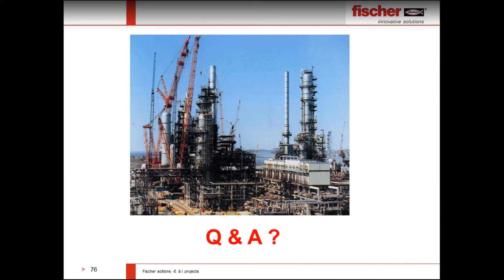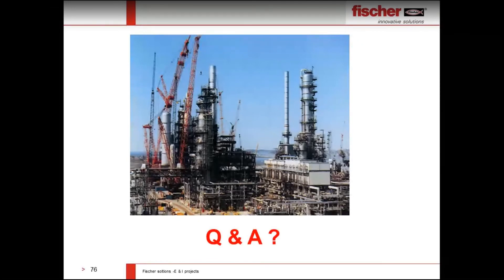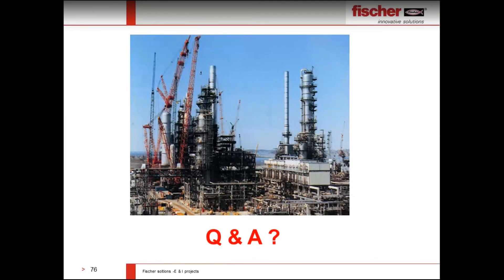HDG is a good solution for structural channels and insulation channel profiles, but for small anchors, we always suggest high corrosion resistance material or duplex stainless steel. Regarding another question: the lifespan of GI-coated material in extreme weather — GI products are for indoor applications only. For outdoor applications, hot-dip galvanized products depend on environmental conditions; lifetime varies from 5 to 10 years depending on galvanization thickness. For our channels at 75 microns HDG, it can go up to 25 years in industrial atmosphere.